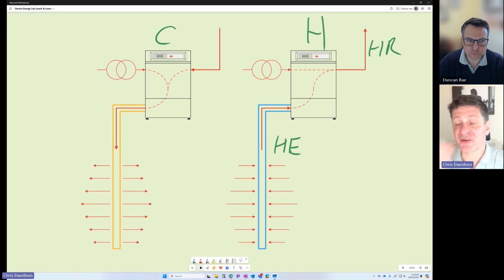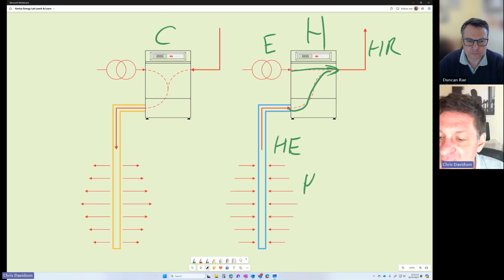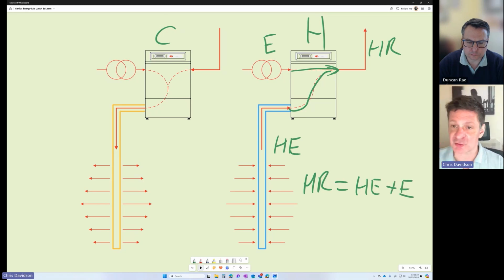In actual fact these systems are one and the same, but I've drawn them as two separate systems for clarity. In heating mode, we take heat from the ground, put it into the building, and use electrical energy to drive the compressor. Through the forces of friction, very close to 100% of that electrical energy ends up as heat on the hot side of the heat pump, added to the heat from the ground. So the heat of rejection into the building is very close to equal the heat extracted from the ground plus the electrical energy.